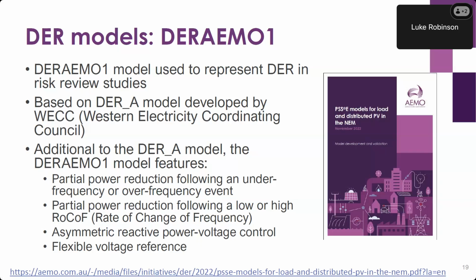So partial power reduction following an over or under frequency event, representing DPV tripping due to frequency over 26 independent stages. Partial power reduction following a low or high rate of change of frequency event, representing fractional DPV tripping over 3 independent stages. Asymmetric reactive power voltage control, so separate proportional gains in response to under or over voltage conditions, and a flexible voltage reference, such that the under voltage and over voltage tripping behavior scales independently of the initial transmission bus voltage. And I've provided a link there with some more details if anyone's interested in that.